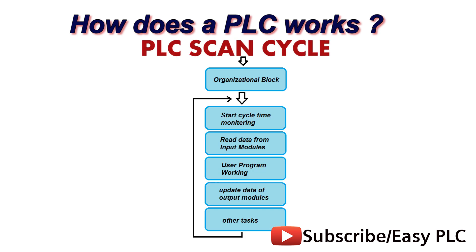How does a PLC work? The working of a PLC can be easily understood as a cyclic scanning method known as the scan cycle. A PLC scan process includes the following steps: The operating system starts cycling and monitoring of time. The CPU starts reading the data from the input module and checks the status of all the inputs. The CPU then executes the user or application program written in relay ladder logic or any other PLC programming language. Next, the CPU performs all the internal diagnosis and communication tasks. According to the program results, it writes the data into the output module so that all outputs are updated. This process continues as long as the PLC is in run mode.